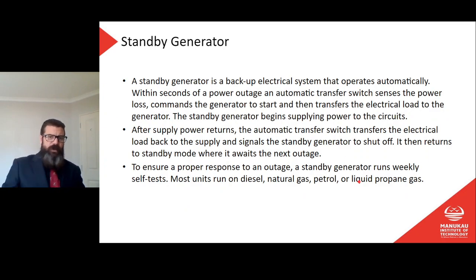Standby generator. A standby generator is a backup electrical system that operates automatically. Within seconds of a power outage, an automatic transfer switch senses the power loss, commands the generator to start, and then transfers the electrical load to the generator. The standby generator begins supplying power to the circuits. After supply power returns, the automatic transfer switch transfers the electrical load back to the supply and signals the standby generator to shut off. It then returns to standby mode, where it awaits the next outage. To ensure a proper response to an outage, a standby generator usually runs weekly self-tests. Most units run on diesel, natural gas, petrol, or liquid propane gas.